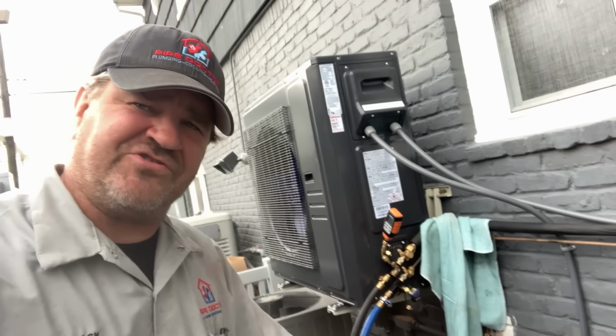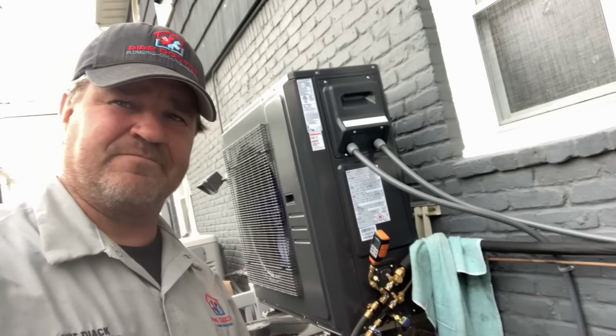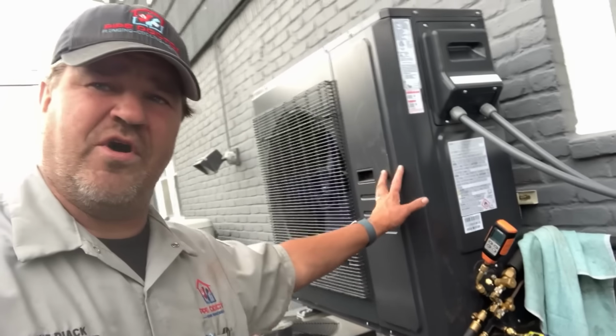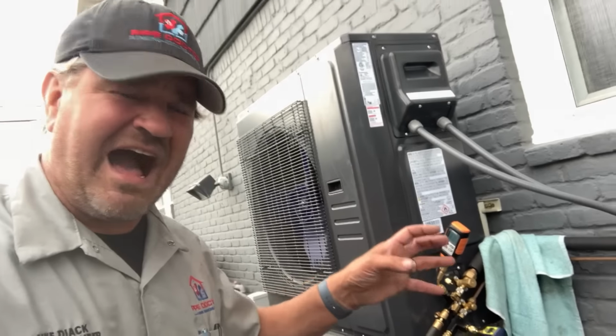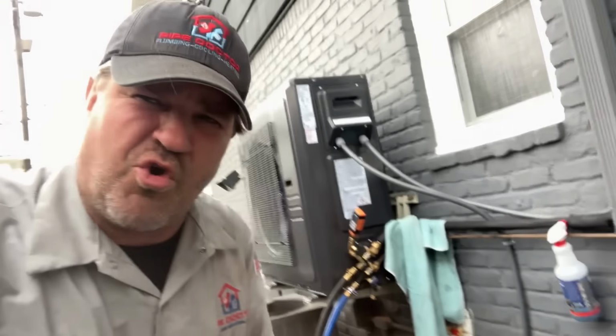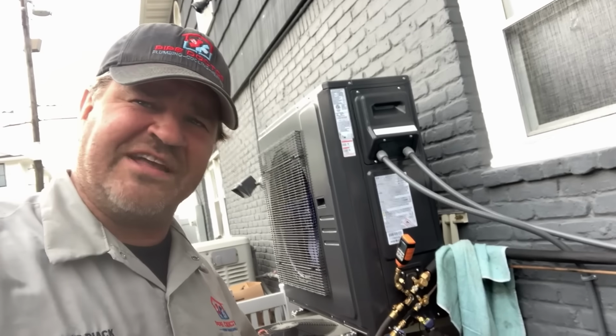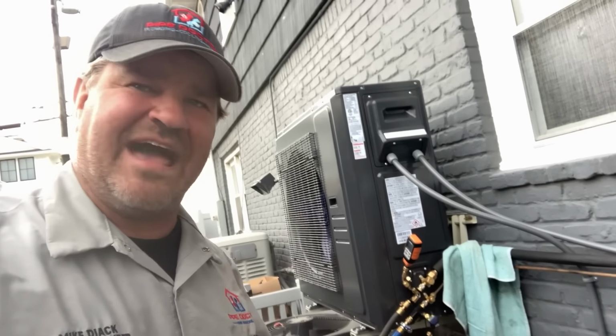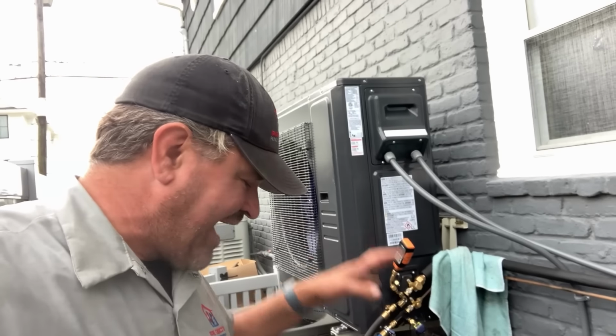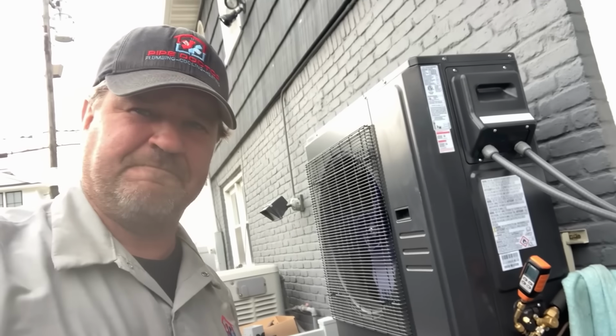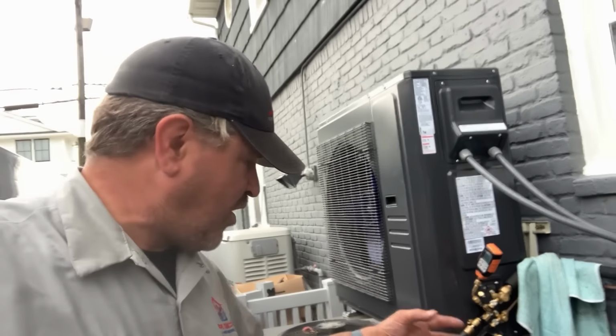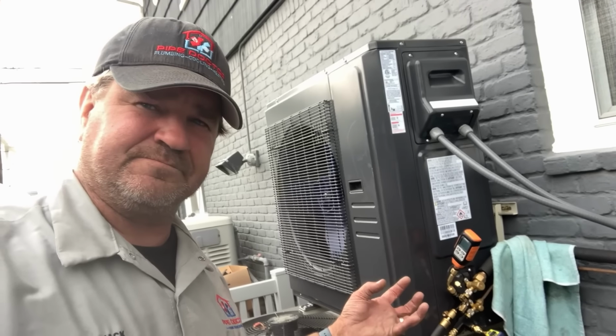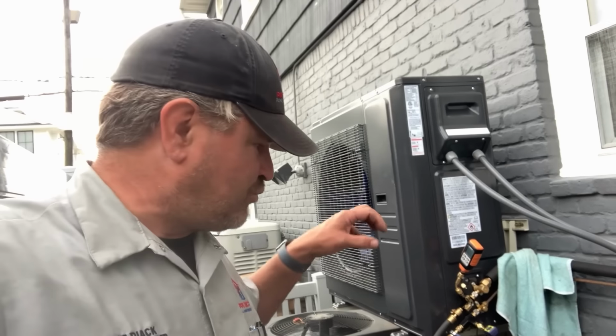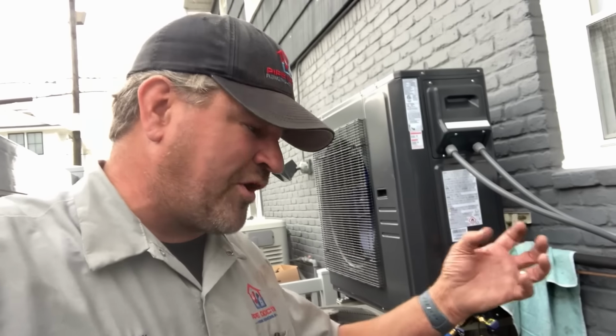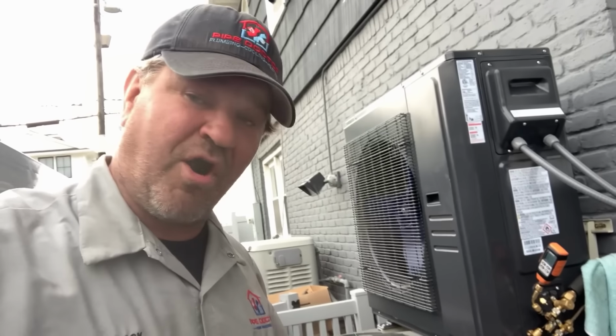Moisture is the enemy. And once moisture gets inside the refrigeration circuit, it mixes with the compressor oil. Modern inverter systems use POE oil, and that oil is extremely hygroscopic. It loves absorbing moisture from the air. Once that moisture gets into the oil, you simply can't boil it out. You can run the vacuum pump and the micron gauge forever, right? You simply can't boil it off, which is what we're doing when we're pulling a deep vacuum. And that's where you've got a problem, when you get moisture inside that POE oil, because that oil loves to absorb that moisture and it doesn't want to part with it.